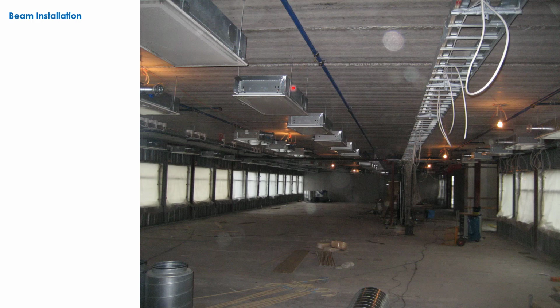In this case, the contractor is using threaded rod. And right now he would have these beams hung a couple of inches above where the suspended ceiling would go in. Notice these have been put in before the ceiling. And then once the ceiling goes in, they would be lowered down into the grid. So these are threaded rods, adjustable to lower the beams down. And then after that, of course, comes roughing in the piping and the primary air ducting.